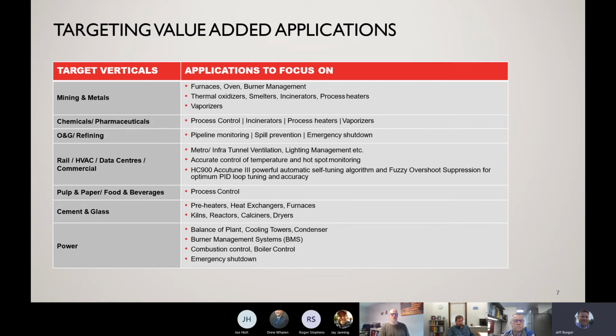The chemicals, pharmaceuticals, so it's great for process control in those areas. In some of those applications, incinerators, process heaters, vaporizers. The refining applications, pipeline monitoring, spill prevention, emergency shutdown. These would require a lot of the SIL 2 rated HC900s. And as you can read through the bottom there's a lot of other applications in different industries that the HC900 works really well in, especially if you're marrying process control with discrete control. The HC900 is really going to outshine a lot of other competition in these areas.